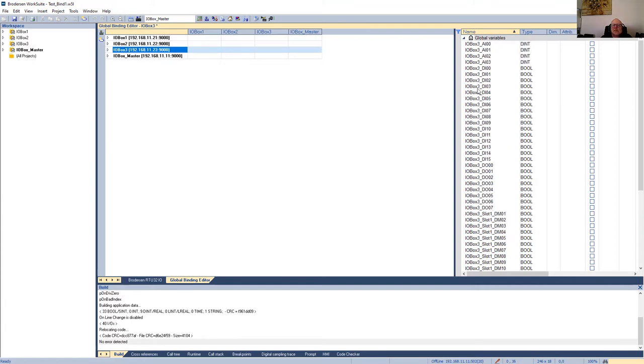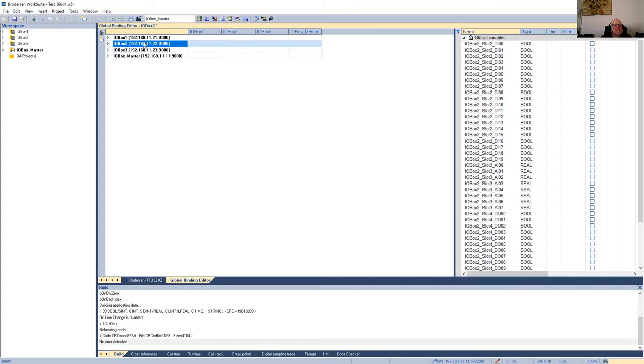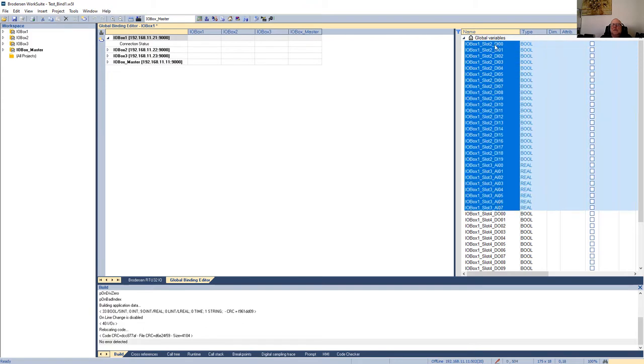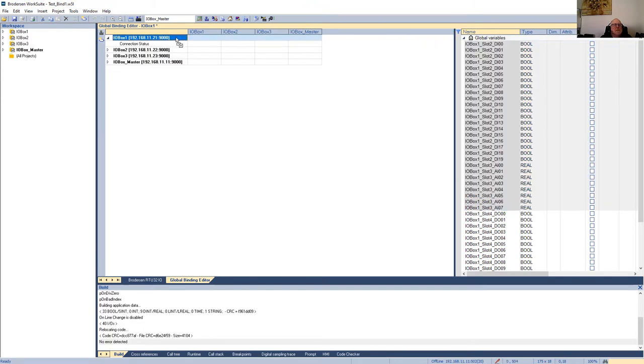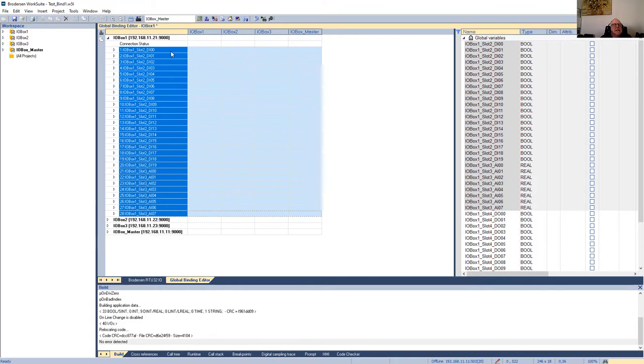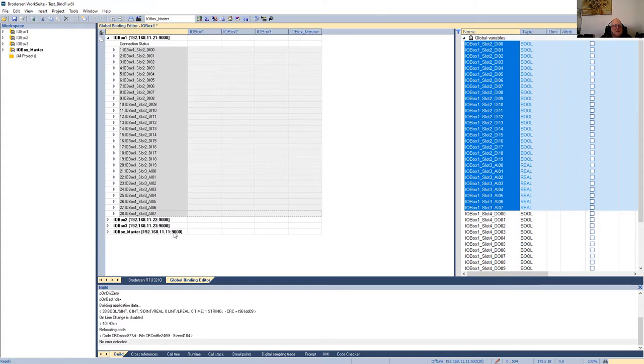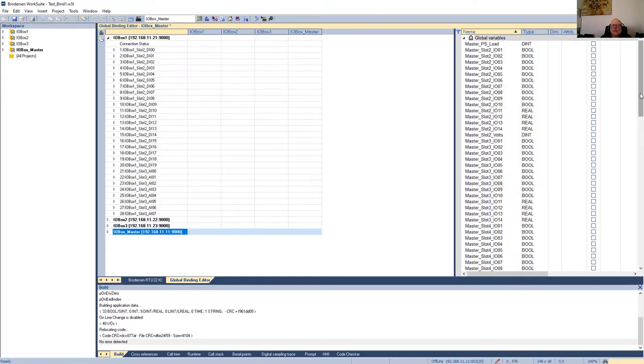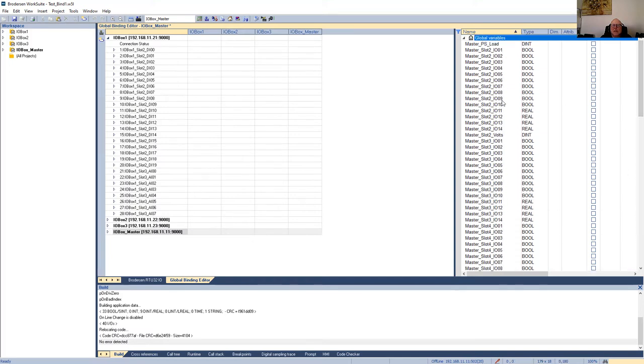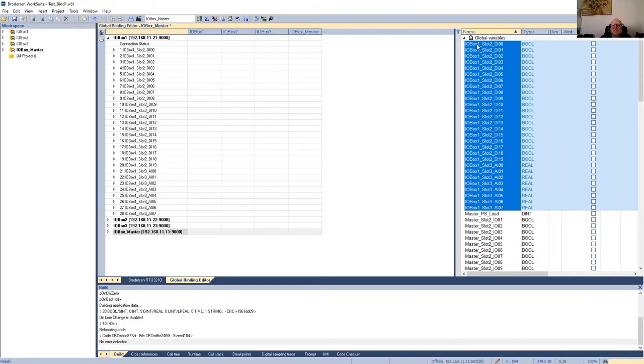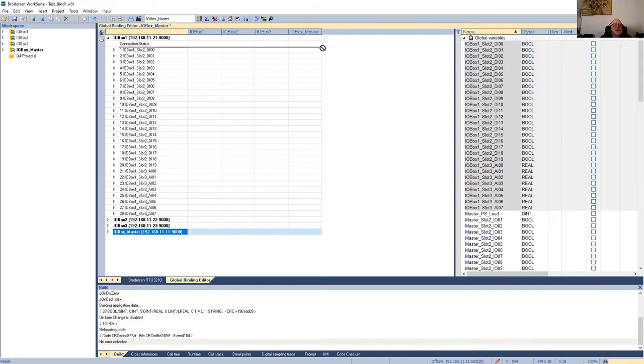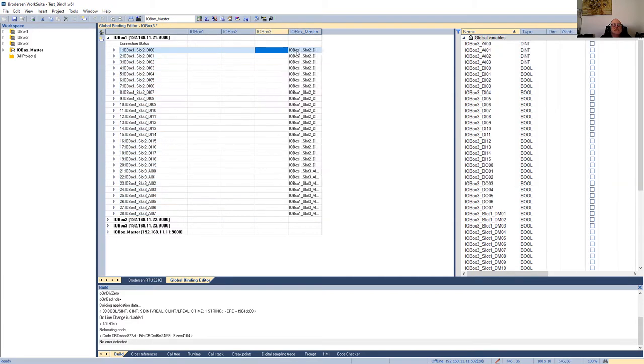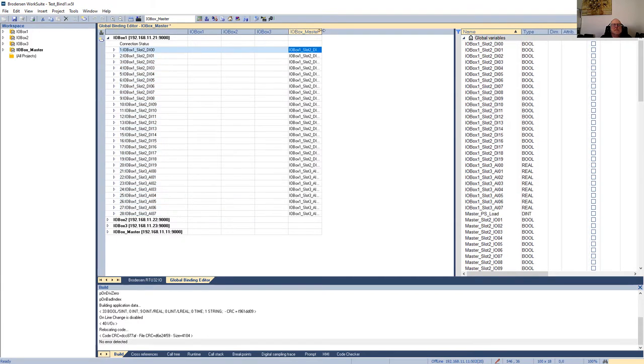I see the variables that are associated to those different sites. I'm connected with I/O Box 1. I can point at its input variables and if I drop them here, they are now going to be produced. So I/O Box 1 knows that it needs to send that data somewhere. If I copy those variables, I go to the master. There's no sort of destination location for that information at the moment. If I just click anywhere and paste in those variables, and if I drag those onto the page, we've now created the association. So I/O Box 1 knows that when this variable changes it sends it to the master to that same variable name that we just pasted in there. So that's enough to make the inputs work.